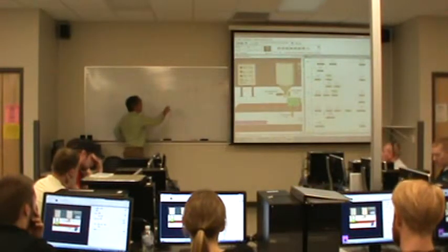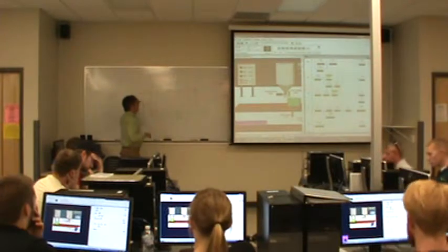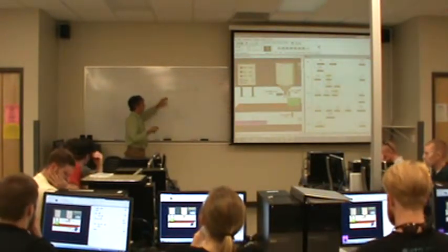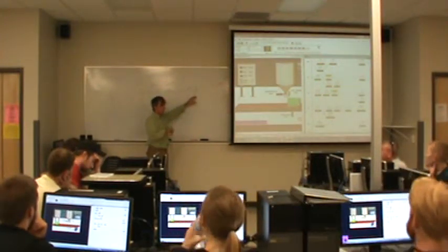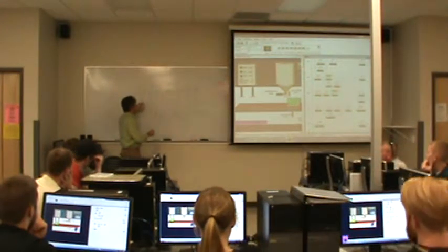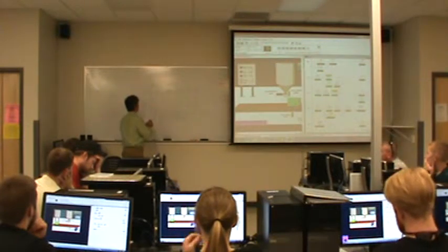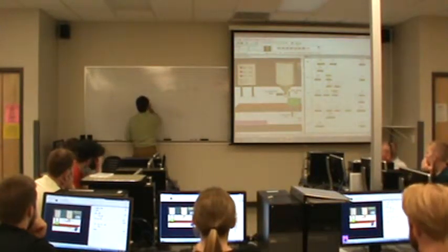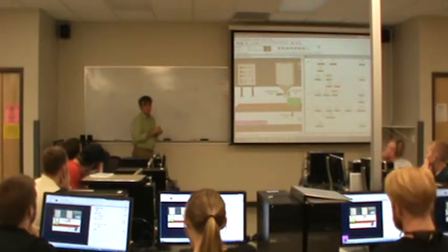Now let's go back and check this and make sure this is correct. If we have not observed an empty box and prox is off and levels off, we want the motor on, we want the valve off, we want fill off, and we want full off. That still makes sense. If we do not have a full box and prox is not true, level is true, something's weird. Hopefully we never actually observe this, but we may as well just leave the outputs as they are, because we really don't care. We don't really expect to observe this.